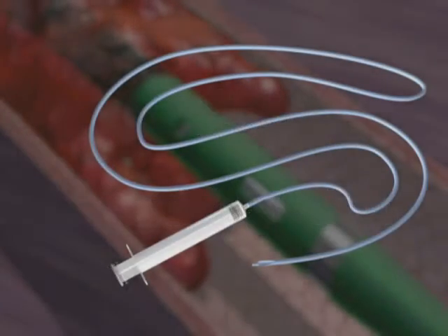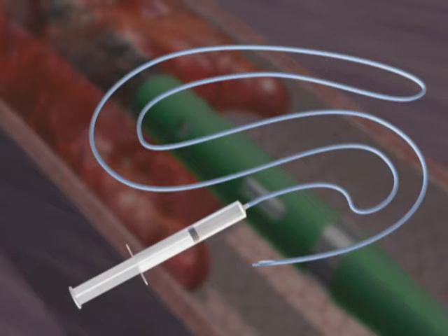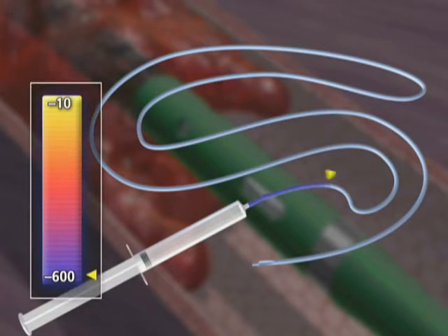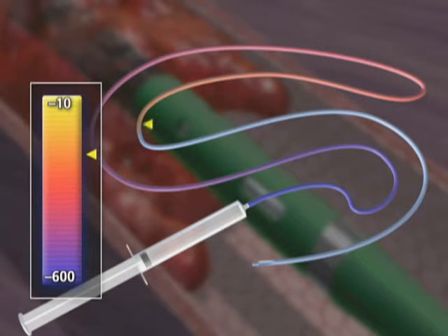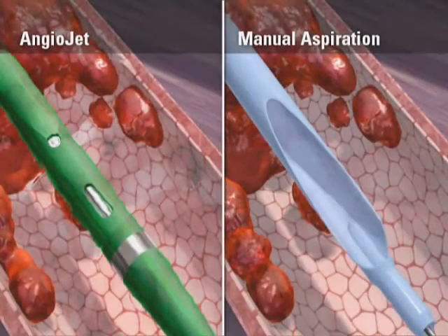Let's contrast this with manual aspiration. Drawing back on the syringe plunger creates a strong negative pressure at the syringe tip, about negative 600 millimeters of mercury. Due to frictional losses, this force markedly decreases along the length of the catheter, so that at the catheter tip, it is only 5 to 10 millimeters of mercury less than systemic pressure, resulting in a very mild vacuum effect. We can see here why AngioJet thrombectomy is superior to manual aspiration.